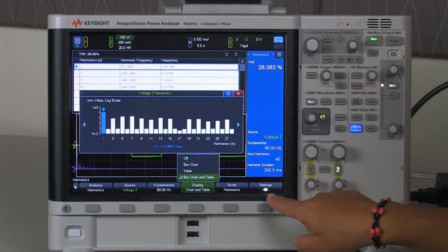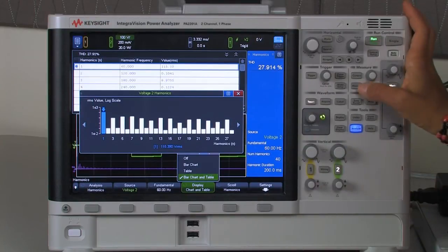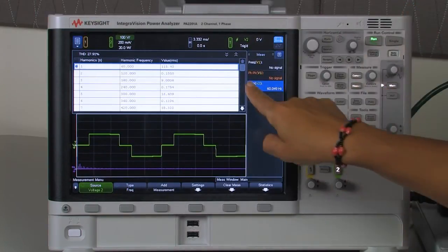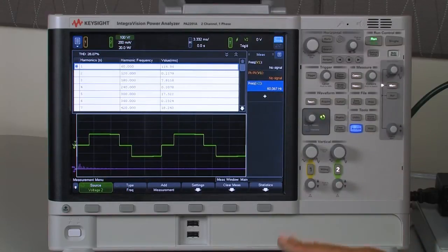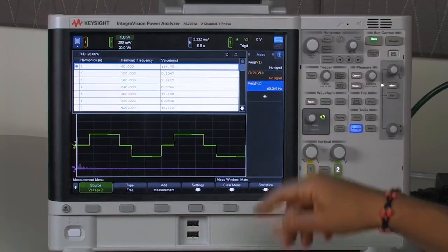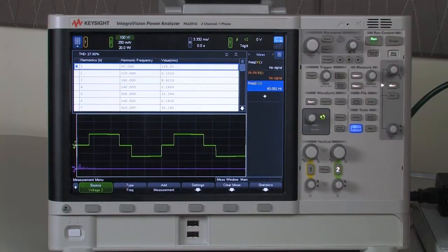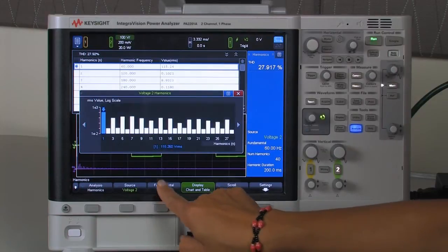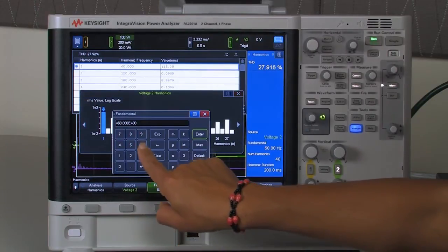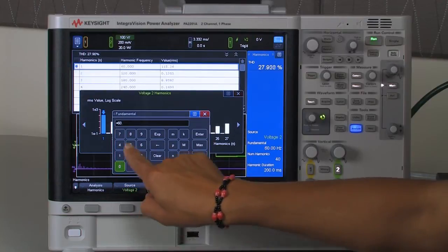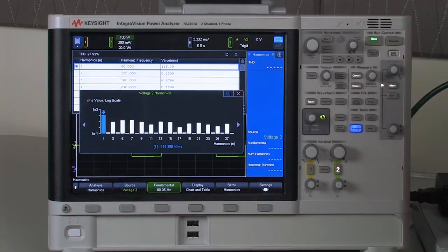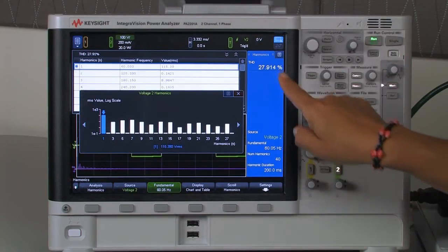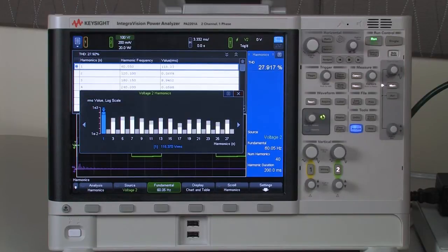Another thing I may want to do is go to measure. If I look at my frequency, actually it's a little bit different. It's not exactly 60 Hz, it's 60.05. So now I can go back to this menu and enter the fundamental frequency more precisely, which will give me a more precise reading.